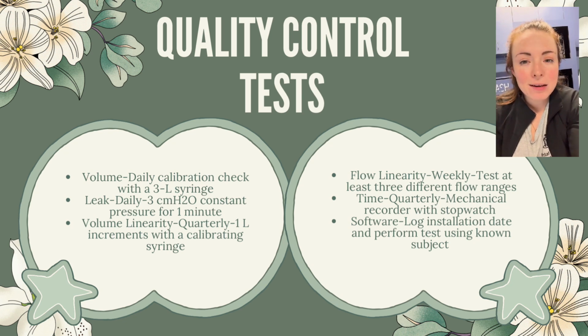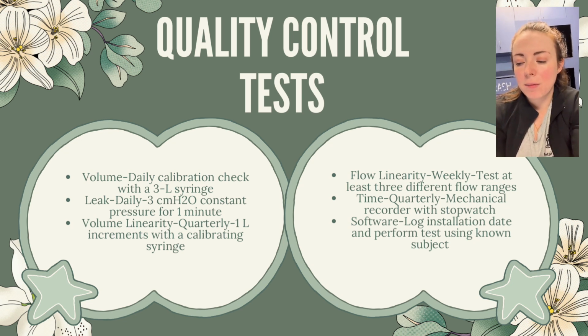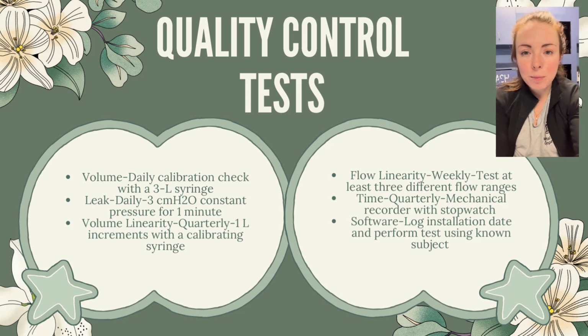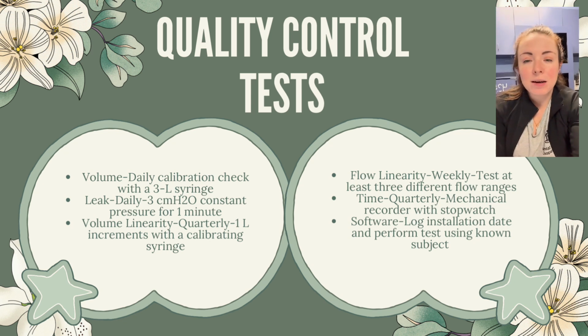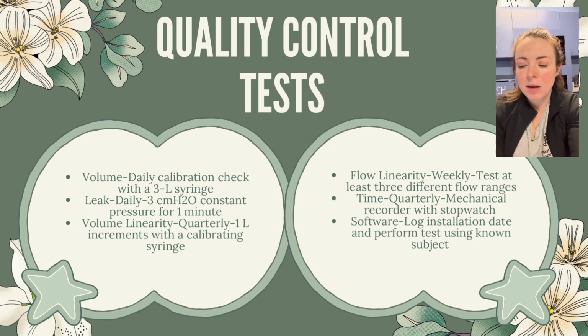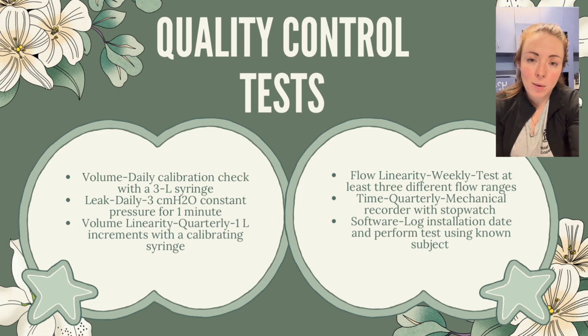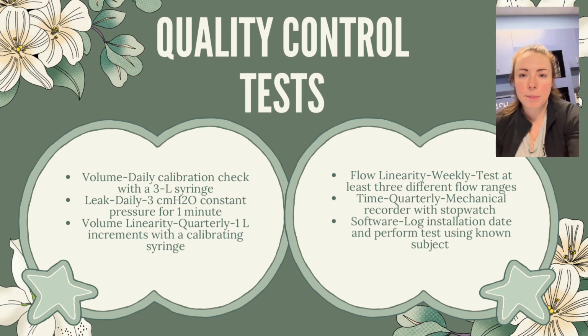There's a time test, which is a quarterly test. It's a mechanical recorder with a stopwatch. And then we got a software test, which is logging installation date and performing tests using a known subject. So all of these tests are required and extremely important, and without them, we cannot have proper PFT data. So that's important to remember.